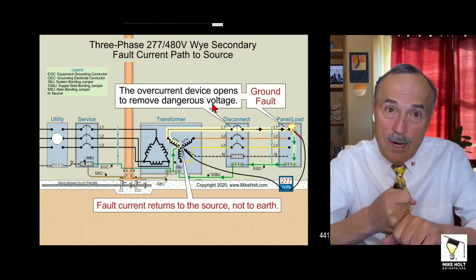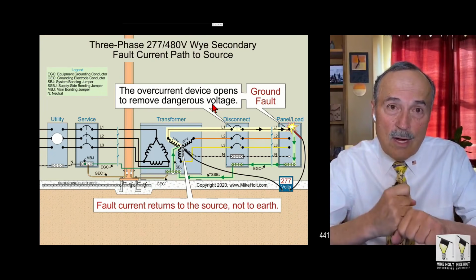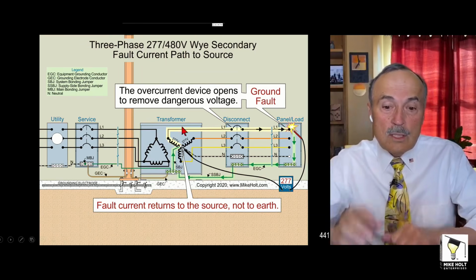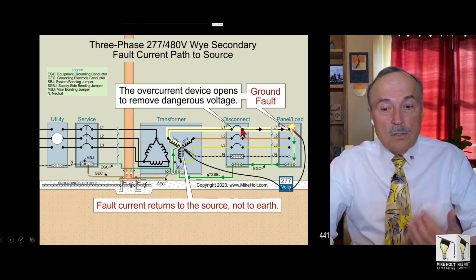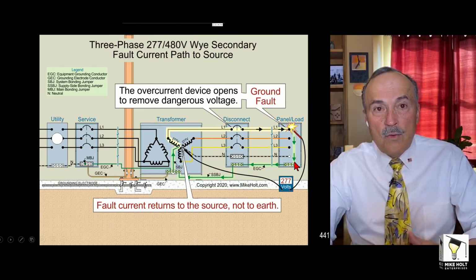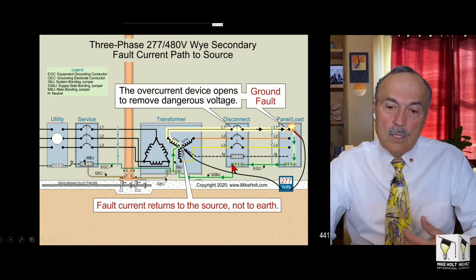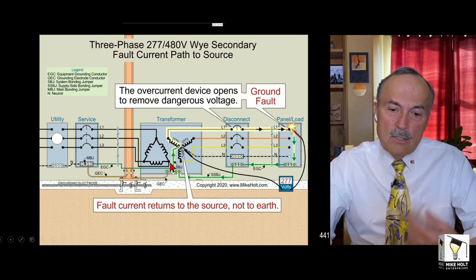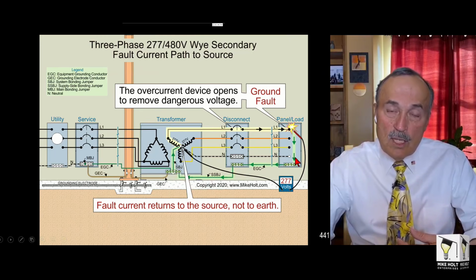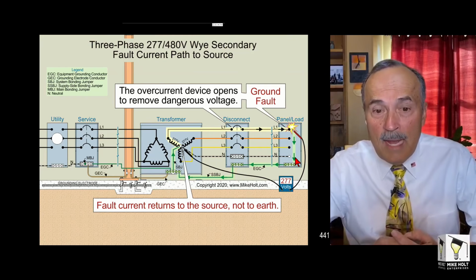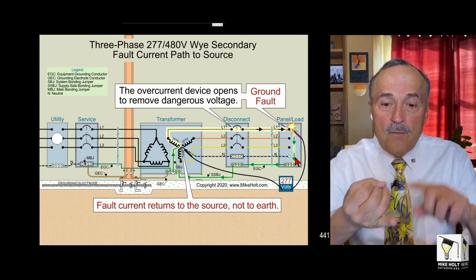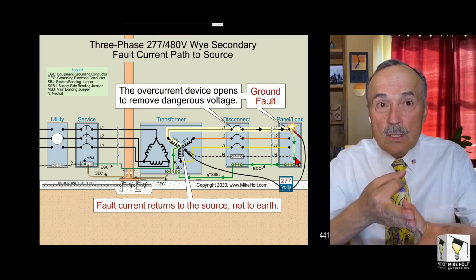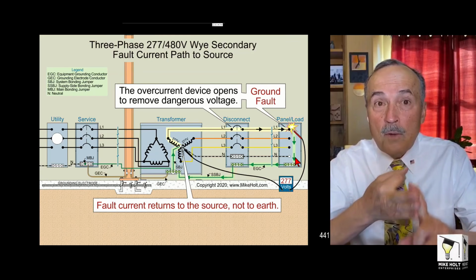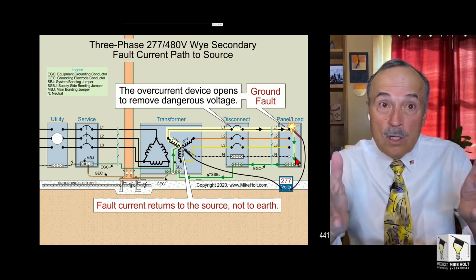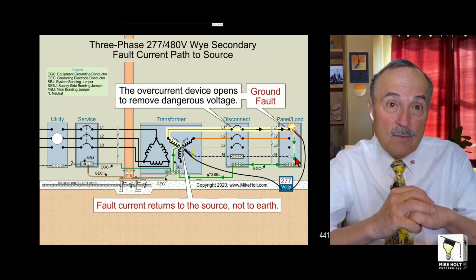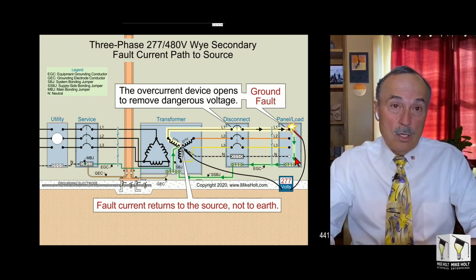What happens if there's a ground fault? Fault current doesn't go to ground. You don't drive ground rods. You don't go to ground, right? Electrons leave the source and travel back to the source. They leave the winding, go to the overcurrent protection device, there's going to be a ground fault, it gets to the equipment grounding terminals, on the equipment grounding conductor, to the supply side bonding jumper, to the system bonding jumper. All this green stuff is called the effective ground-fault current path, which is a low impedance path from the point of a fault back to the source, for the purposes of opening or clearing the overcurrent device. That's the Article 100 definition of an effective ground-fault current path. Electrons aren't going to ground.